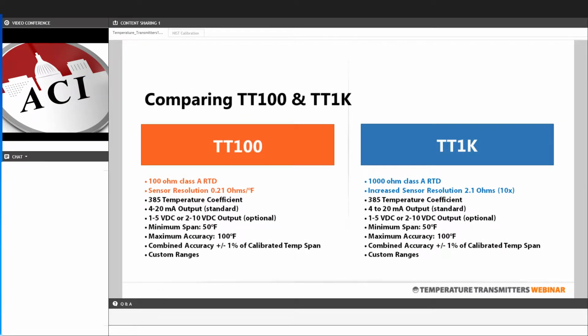Our temperature transmitters use a 100 or 1000 ohm platinum RTD as the underlying base sensor in these units, and that's signified in the part numbers by using TT100 or TT1K, TT standing for temperature transmitter. The main difference between these two is that the 1000 ohm RTD is going to offer a higher level of resolution, and that simply means that it takes less of a change in temperature to move the ohm value 1 ohm in either direction, warmer or cooler.